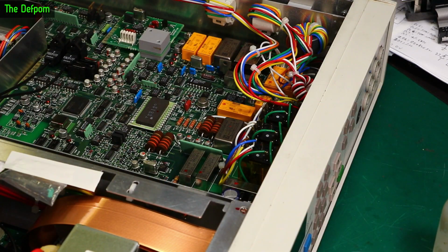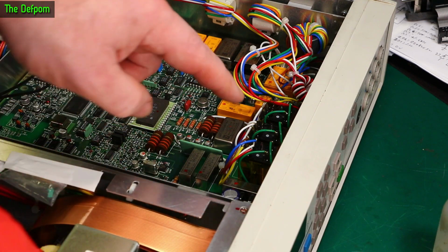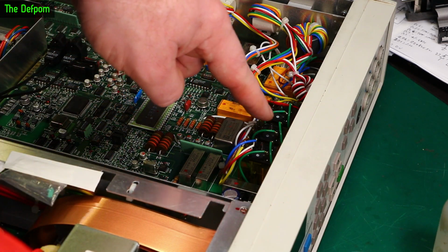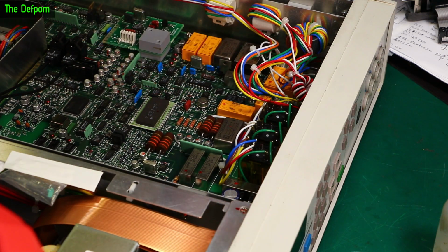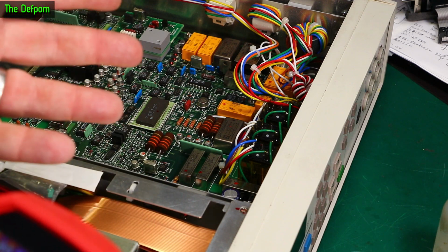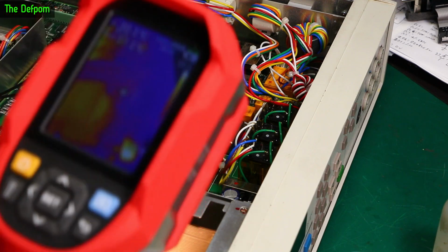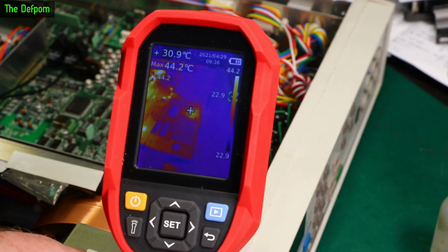So I've had this thing powered up now for probably 5 minutes. Not very long really. So the middle relay is currently active. So this one right here. That's the one which is K006, which is known to have a programming issue with the logic, apparently. And there's a modification listed for how to resolve that problem. This is obviously causing thermal EMFs because it's getting hot. And the crosshairs are on that relay.